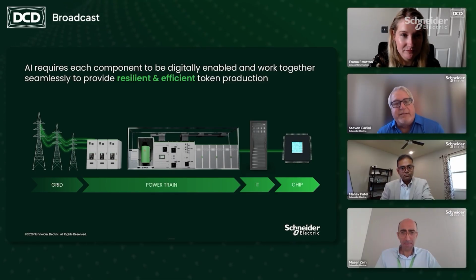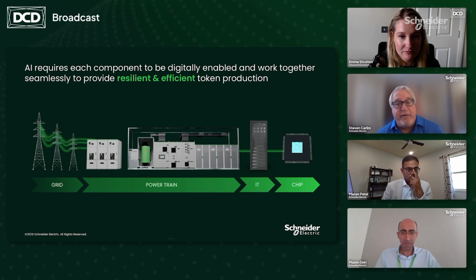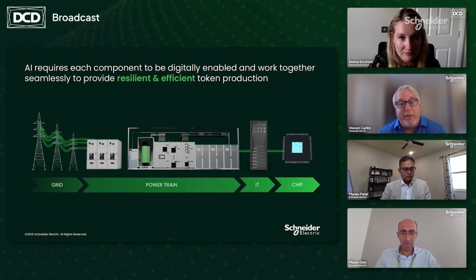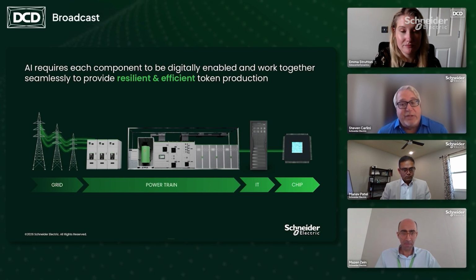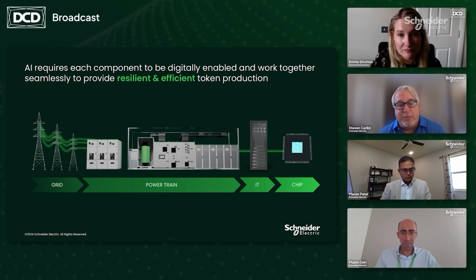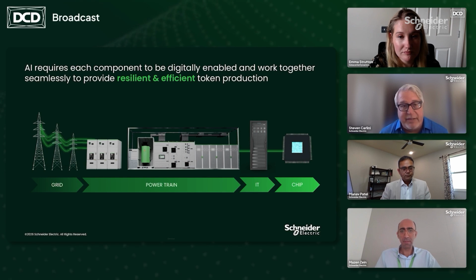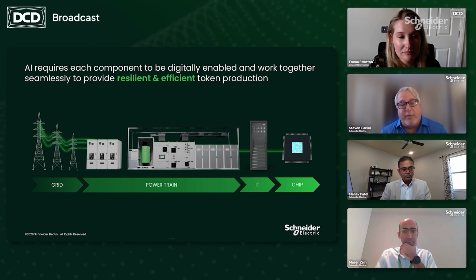What that means is taking the electricity all the way from where it's generated - the power station on the grid - all the way to the actual GPUs or CPUs in the server. It's one continuous electrical connection, but it starts off as high voltage, then it's transformed to medium voltage. That's really where the data center or building comes in, taking medium voltage - 10,000 to 39,000 volts - bringing it down to low voltage, then to the room, usually around 400 volts, then to the servers, around 56 to 60 volts, and down to 5 to 12 volts for the servers themselves.